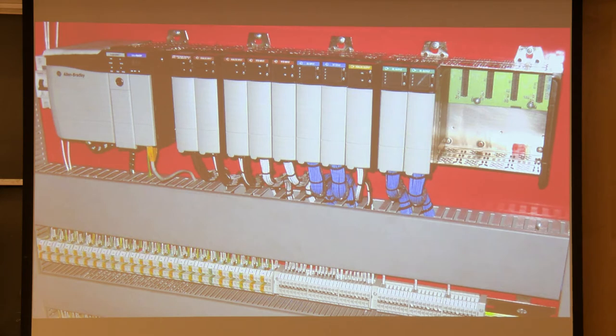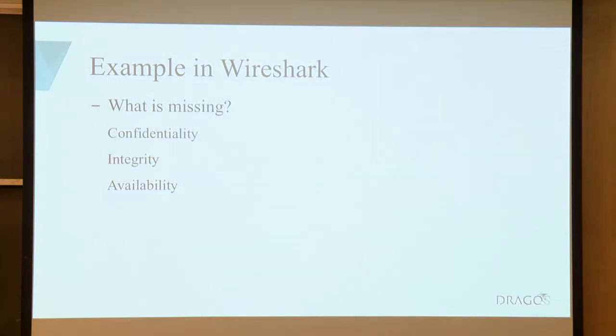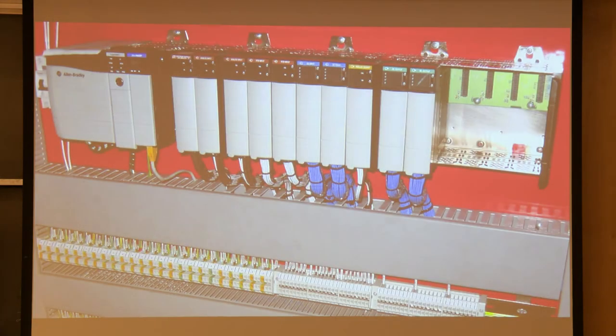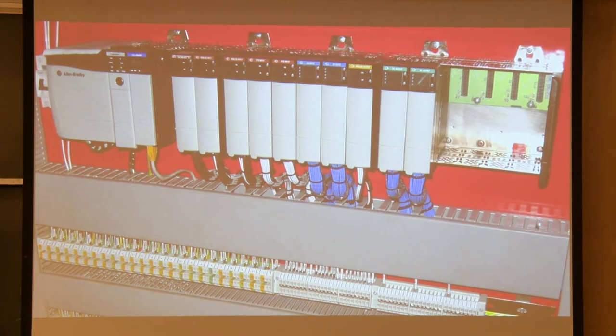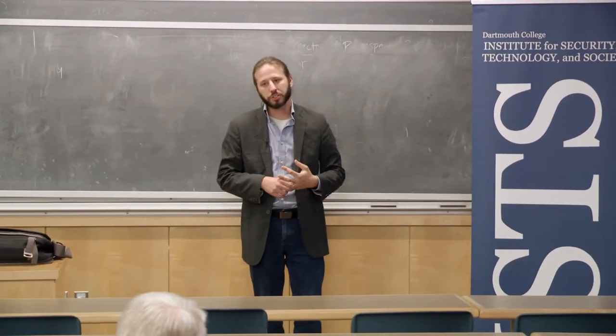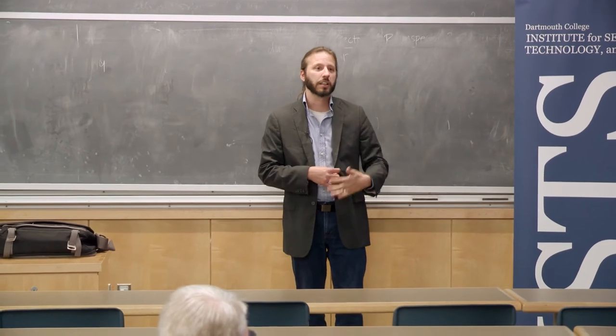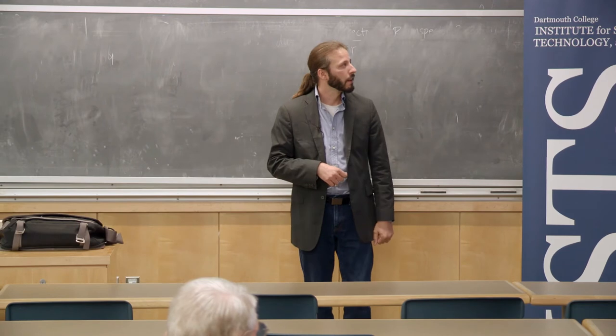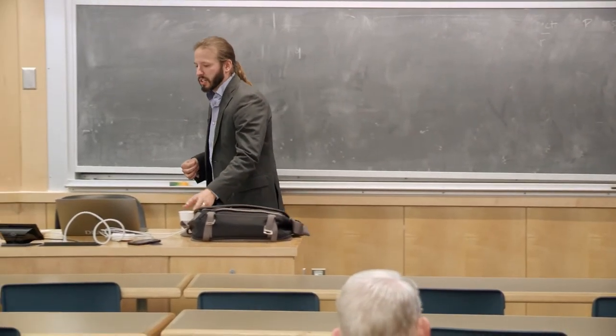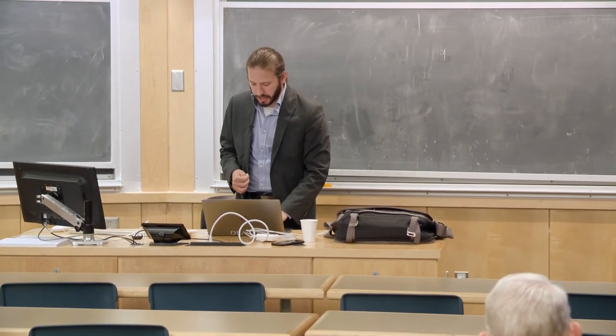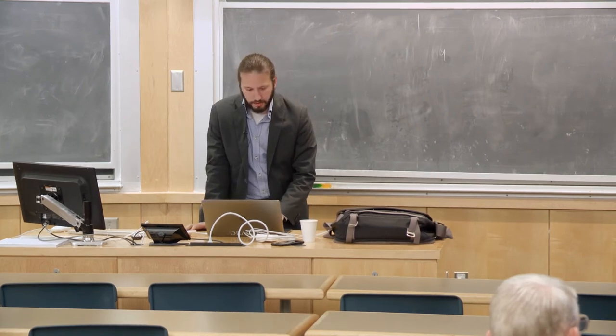So serial devices are connected through those electronically. But you'll also see there's an Ethernet jack plugged into one module. So the field devices themselves may be discrete devices communicating to that one module, but that's then fed to another PLC or a master unit, eventually fulfilling the rest of the process needed. Maybe this is one of several PLCs inside a substation, and those in aggregate are sent to a control center used by a system operator to maintain the balance of the grid from a demand response perspective. I mentioned coils and registers, and I actually have an example of what that data looks like from the network side.